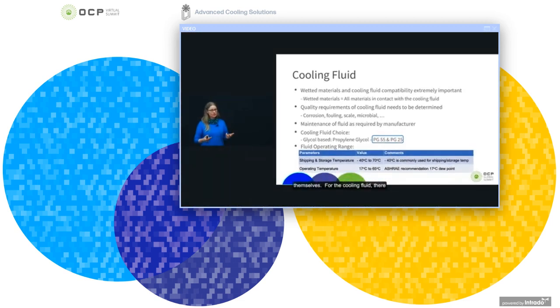For the cooling fluid, there are many different choices for liquids that can be used. You can have water with additives, you can have glycol-based liquids, you can have dielectric liquids or refrigerants. What we have been focusing on within Intel is glycol-based and particularly propylene glycol-based liquids. So we've been focusing on the propylene glycol with 55% glycol and 25% glycol. The reason for that is really the fluid operational range that we need to adhere to. So for shipping and storage, we need to make sure that the liquid is not freezing if we go below minus 40 Celsius. And this is why we have to go to a 55% glycol level. So this is really the liquid that we would use for shipping and storage. And then the operational temperature range goes between 17 Celsius up to 65 Celsius.